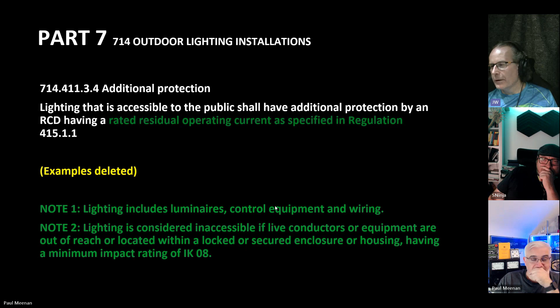That seems fair. The problem I've got with that Note 2 is it's always saying it's inaccessible if it's in a locked cabinet, but what if there was a problem and a fault occurred and that metal cabinet became live? Someone could still touch it and get a shock, and be killed by it. So why not just put an RCD on anyway? The fact it's in a locked cupboard might secure the conductors away, but if the enclosure is metallic, that's not really protection against anything. It's no different from a lighting fixture with a metal outside that someone could grab hold of and get a shock from. So just put the RCD on it in the first place. Yes.